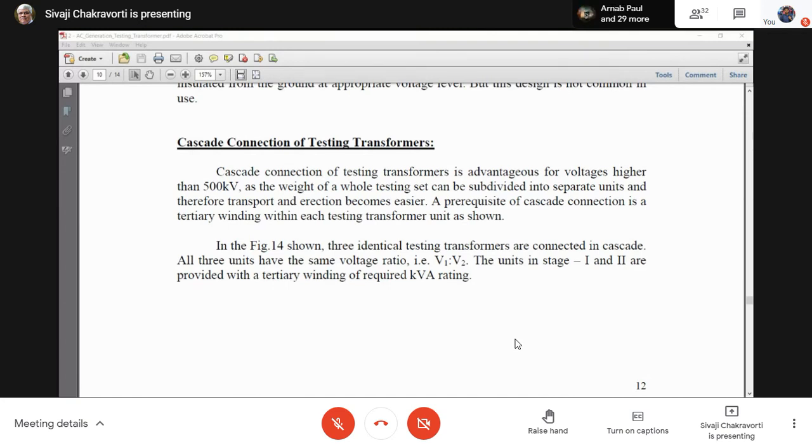So these are really big, when the voltage rating becomes high. So what we always prefer is, say, if I have this diagram that I showed, 1500 kV, now we have two transformers which have 750 kV. Then each one is the size you have seen. But if you think of one at 1500 kV, it's impossible. I cannot transport it. Just not possible.